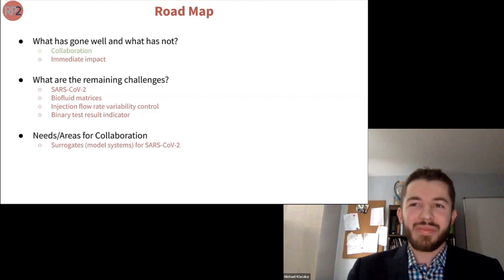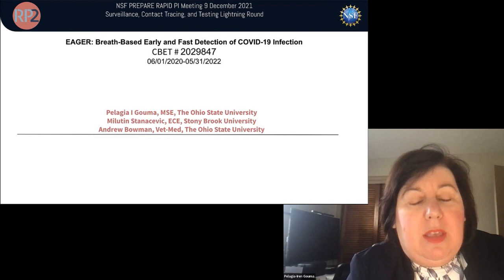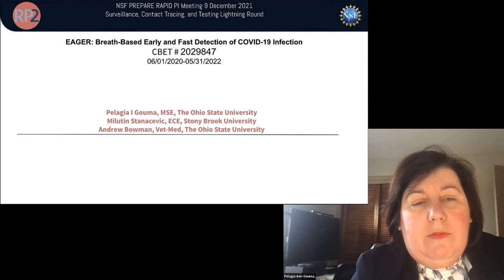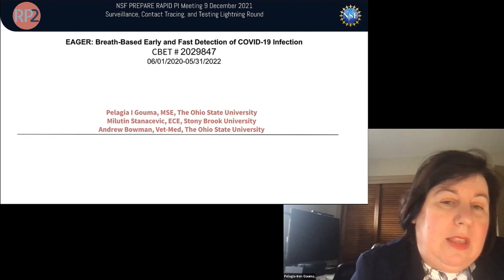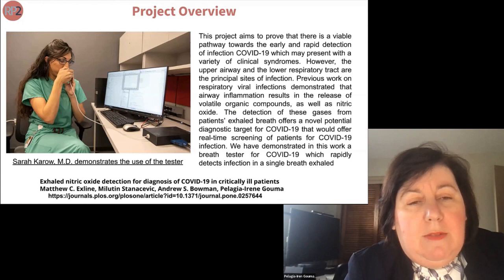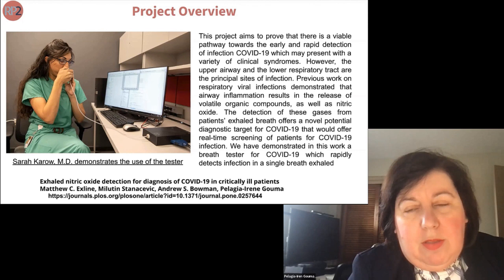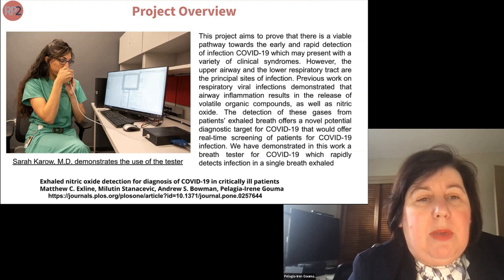I'm the PI for this EAGER grant, which has an exploratory component in that we developed a breath test for COVID-19 — a non-molecular test. It was a truly interdisciplinary effort involving materials science, electrical engineering, veterinary medicine, infectious disease expertise, and a clinical collaborator, Dr. Matthew Exline. The device — the small black box shown to the left — is the breathalyzer. A physician is shown demonstrating it: someone exhales for 10 seconds and within 15 seconds has an answer whether they have COVID-19.